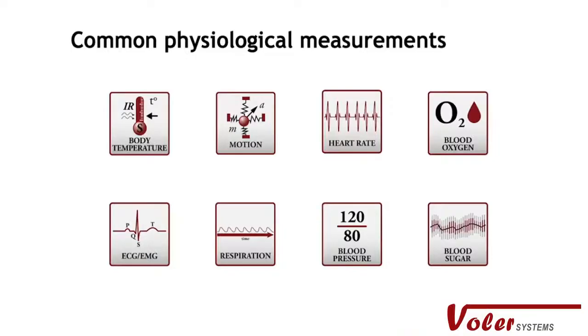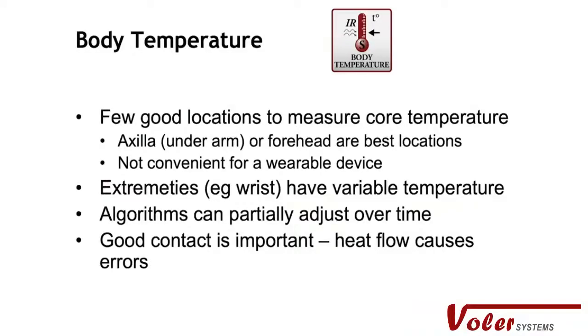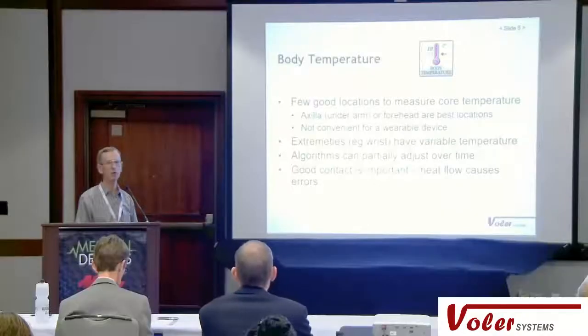I'm going to talk about eight parameters you can measure on the body and some of the limitations. Body temperature seems very straightforward — thermometers are old-fashioned. The difficulty is that what you really want to measure is the core temperature, but what you're measuring is the skin temperature. On the wrist, skin temperature may be very different from core temperature if you're in a cold room or outdoors. You can improve that measurement by fusing other sensors — for example, if you know the air temperature is cold, or if an accelerometer detected rapid motion indicating exercise, you can turn a poor measurement into a much more accurate one. This is called sensor fusion.